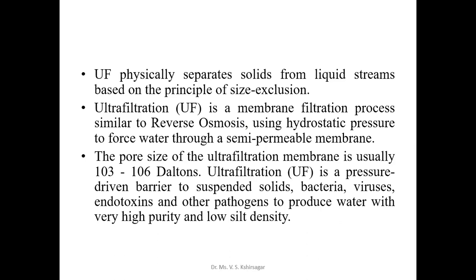So ultrafiltration is a membrane filtration process similar to reverse osmosis, as I said just now, using hydrostatic pressure to force water through a semi-permeable membrane. We need to apply pressure to push the water in a forward direction, and it will also pass through the ultrafiltration membrane. It is another type of membrane. The way we use a semi-permeable membrane in reverse osmosis, here we use an ultrafiltration membrane, a different type of membrane. The technology we use in reverse osmosis is the same here in ultrafiltration.